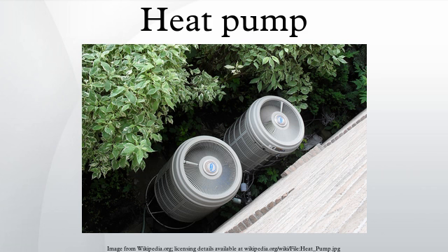Heat pumps use a refrigerant as an intermediate fluid to absorb heat where it vaporizes, in the evaporator, and then to release heat where the refrigerant condenses, in the condenser. The refrigerant flows through insulated pipes between the evaporator and the condenser, allowing for efficient thermal energy transfer at relatively long distances. Reversible heat pumps.